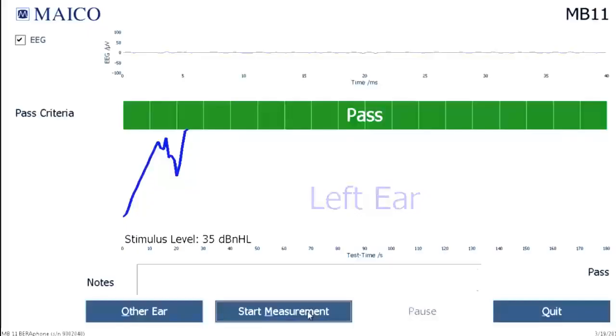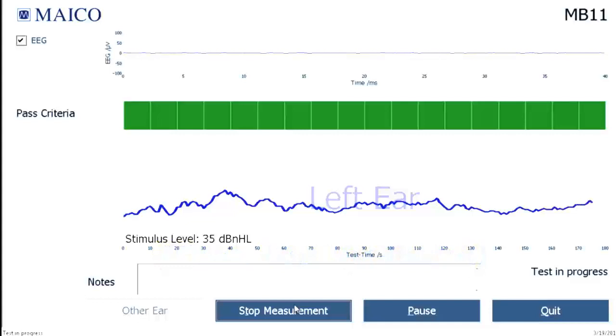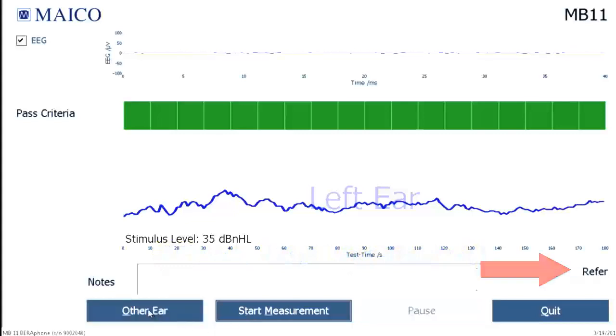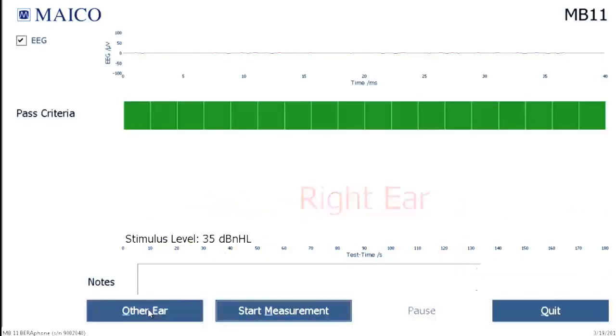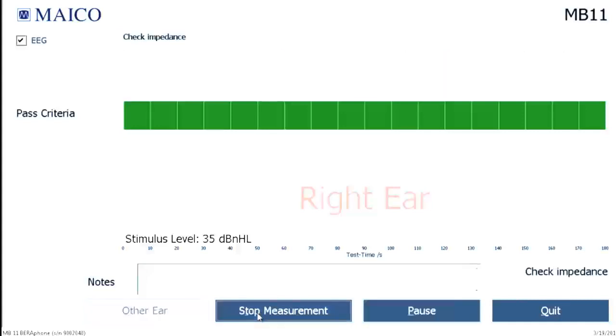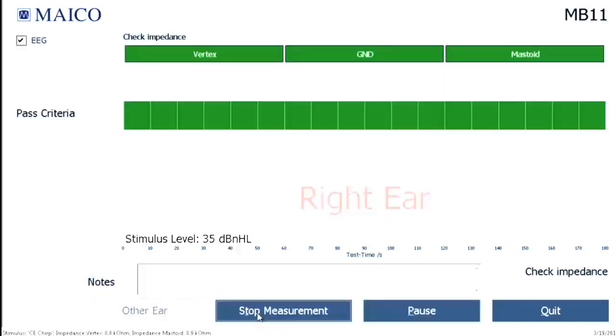When the data collection line ascends and moves into the green area at the top of the graph, a pass result will display and the test will stop automatically. After 180 seconds of good ABR data samples have been collected without the line crossing into the green area, the screening will stop automatically with a refer result. When the screening is complete on one ear, select the other ear button on the measurement screen to change the test ear. Prepare the baby for testing the other ear and select Measure when you're ready to begin the screening.